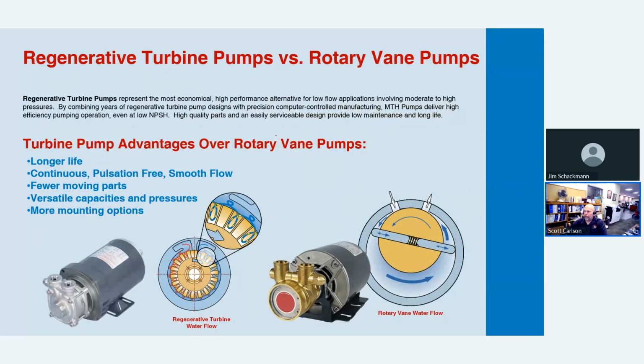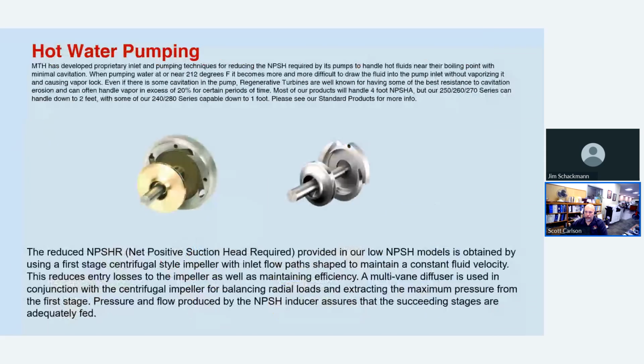Another advantage over a rotary vane is that a rotary vane will have sliding parts and parts that rub constantly, as well as pulsation. With a regen turbine, because the impeller is balanced and no parts make contact, you'll have much longer life. You do get the pulsation-free movement, and there's several different capacities and pressures available. And we can do several different mountings.